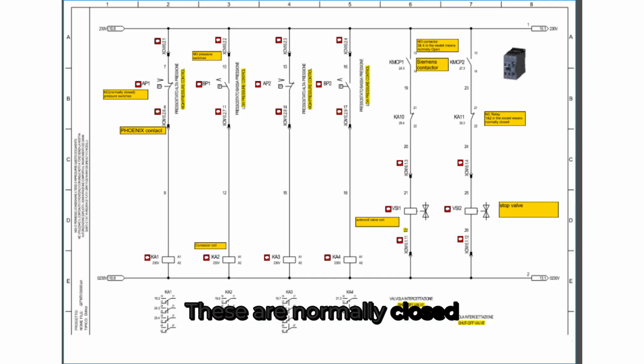These are normally closed solenoid valves, meaning they remain shut until the controller energizes the relay coil. When the coil is powered, the valve opens, allowing refrigerant flow through the system.